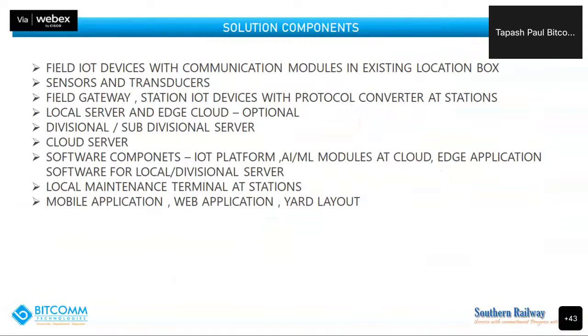The solution component is the field IoT device. One is the field IoT device with communication modules, which is in the existing location box, so we do not need any extra location boxes. Sensors and transducers are needed, such as voltage sensors and current transducers. There's also the field gateway, station IoT device with protocol converter at the station. The protocol converter is required when we need to integrate with the AI data logger or MSDAC system.